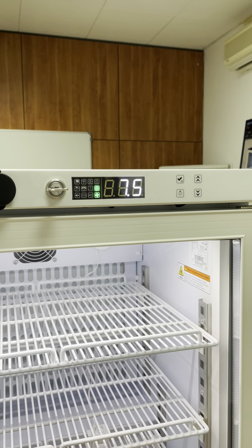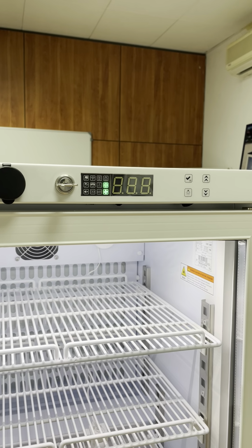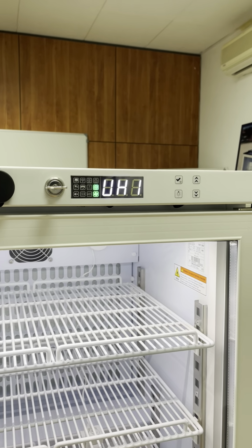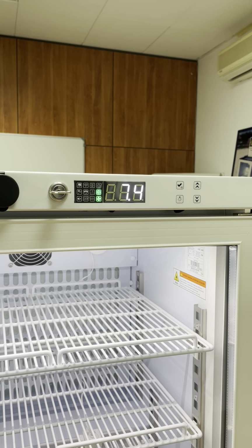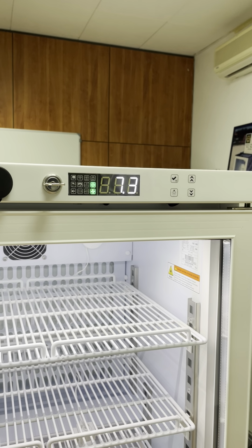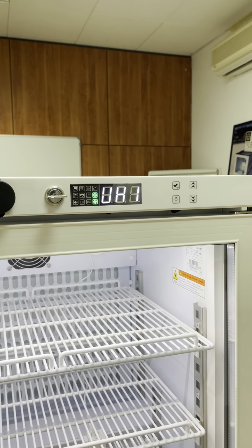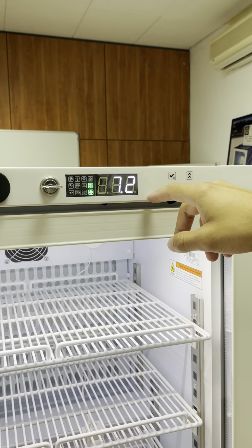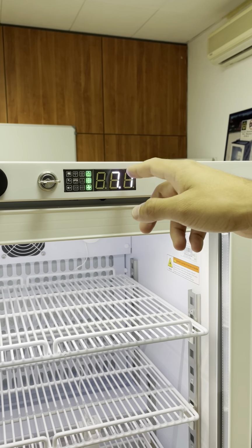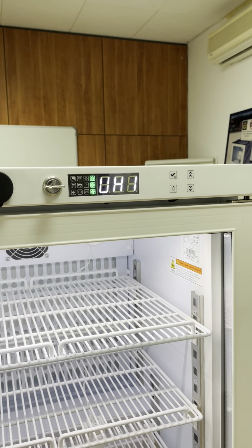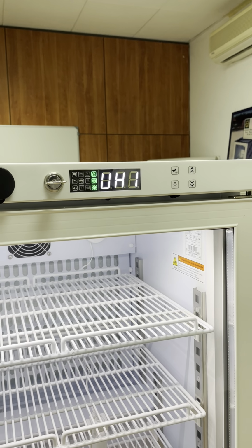Also during the night the energy went out, but then the energy comes back again, still during the night. If nothing registers that there was an alarm during the night, then when you arrive in the morning, we look at the equipment and you will see that the temperature is below 8 and you think everything is okay. You don't know that there was a power failure during the night.